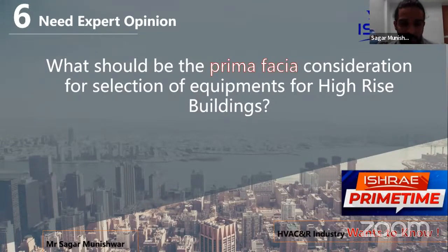The reason, one reason I spoke about, is the stack effect. If you have a stack effect, the air will try to penetrate from the bottom and go up, which can impact the pressurization system. So it is better to have fans selected for, say, 10 floors, 11 floors. I'm just taking a number, but I'm saying have the pressurization system divided among all the floors so that you can maintain the required 50 Pascal pressure between the staircase and the adjoining areas as stipulated in various codes, which means you need to have a number of fans located at a number of floors.